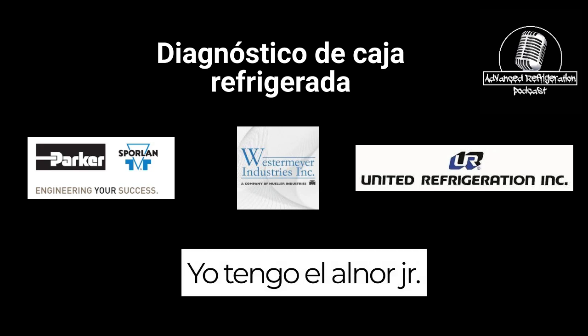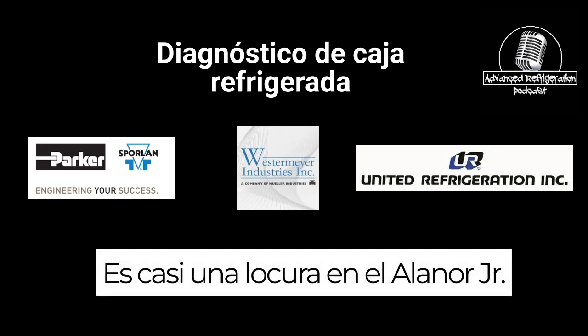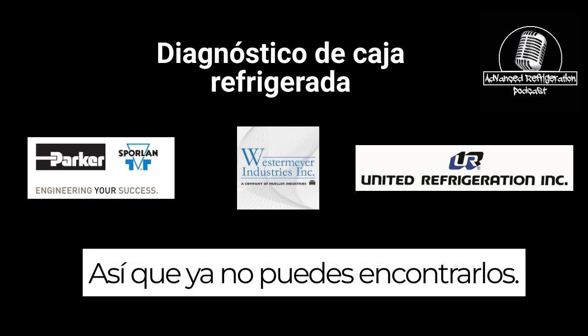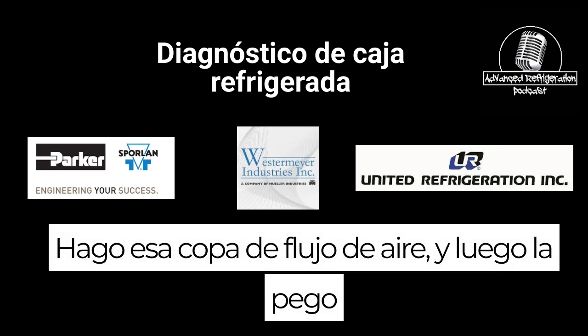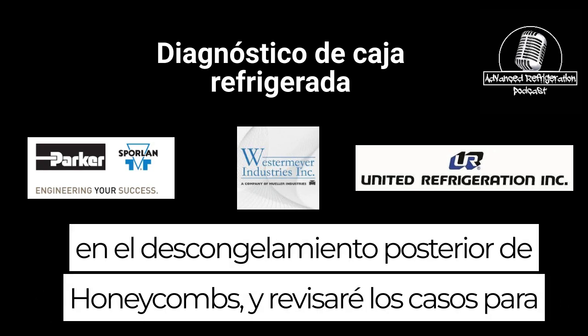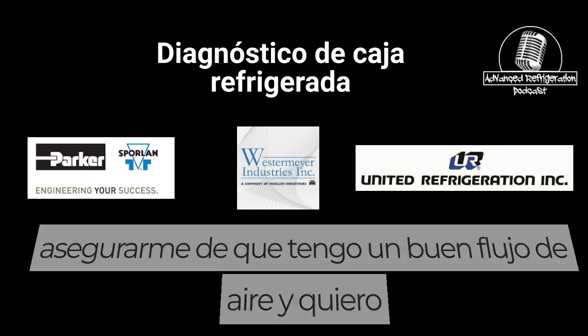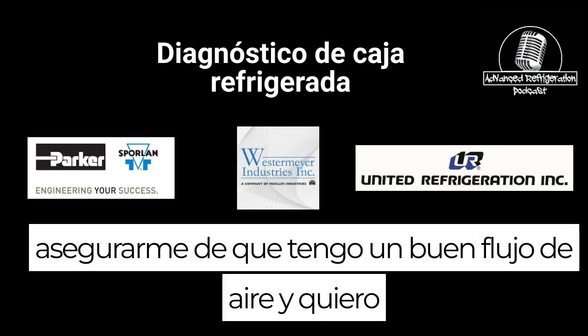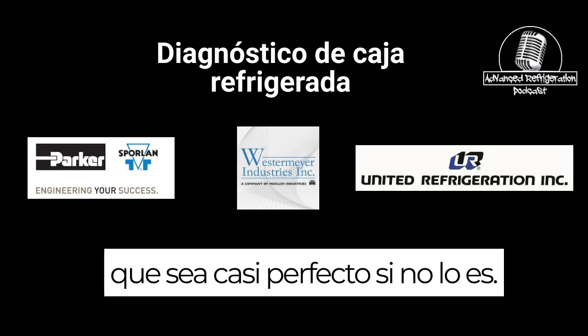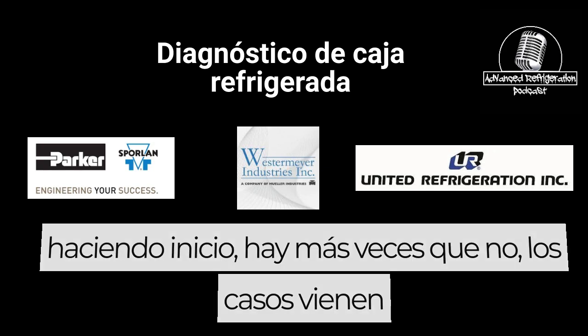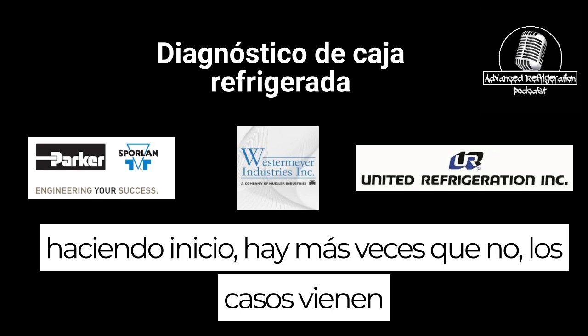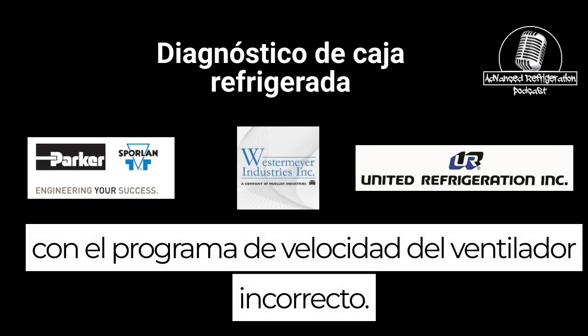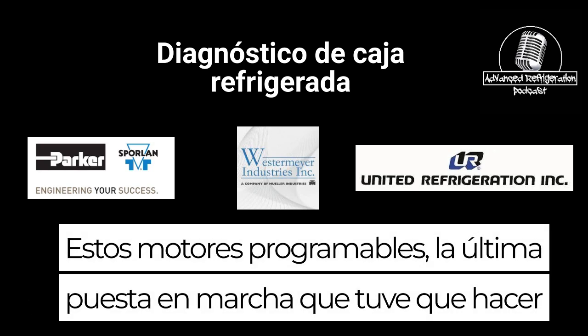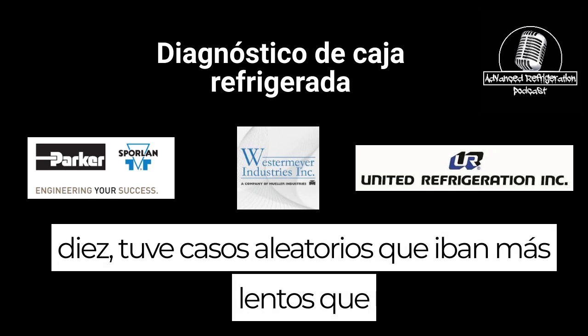I have the Alnor Junior. It's almost dead nut on with the Alnor Junior. You just can't find them anymore. But I make that airflow cup, and then I'll stick it up in the honeycombs post defrost and check the cases to make sure that I actually have good airflow. And I want it to be almost spot on. There's a lot of these cases out here, especially doing startup, more times than not, cases come out with the wrong fan speed program in these programmable motors. The last startup I had to do, 10 cases, I had random cases that were running slower than others.